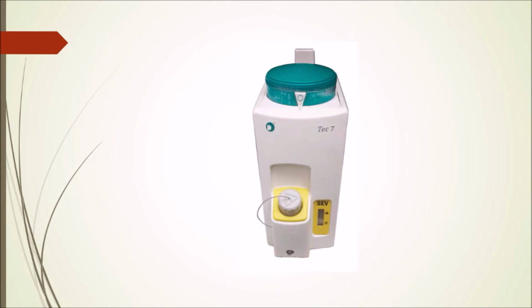Inhaled anesthetic agents, except for nitrous oxide, exist at ambient temperature and pressure as liquids at sea level, which must be evaporated by a vaporizer. Vaporizers add a controlled amount of anesthetic vapor to the gas mixture. The purpose of a vaporizer is to add anesthetic vapor into the fresh gas flow in a way that the output of the vaporizer delivers the set concentration of the anesthetic agent accurately.